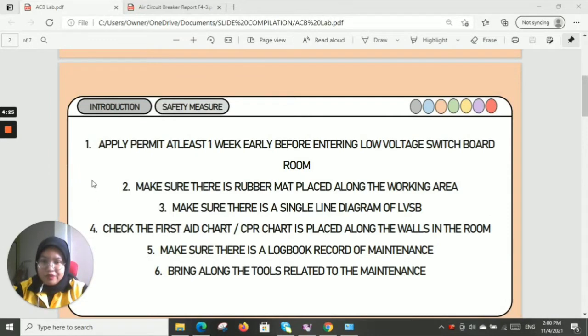The first safety measure is to apply permit at least 1 week before entering the LVSB room. We also need to make sure there is a rubber mat placed along the working area, and a single line diagram of the LVSB before we handle any circuit breaker. The most important thing is to check that the first aid chart and CPR chart are placed along the walls or within the room.